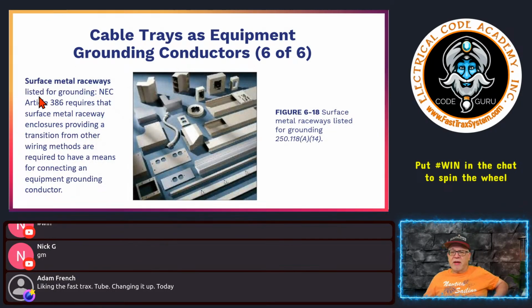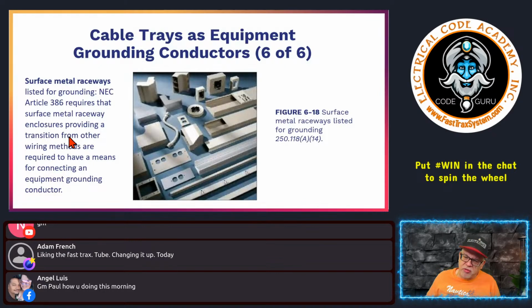Okay, so this is an example of some surface metal raceways, right? So you see these things, it looks like the plug mold, the metal plug mold, that's surface metal raceways, things like that. We saw that in 250.118(A)(14). We saw that one, all right? Let's see here. So those are evaluated, okay? Now it says listed for grounding, NEC Article 386 requires that surface metal raceway enclosures providing a transition from other wiring methods. So basically you're going from, let's say, a raceway, right? And transitioning into an end knockout on one of these surface metal raceways, okay?